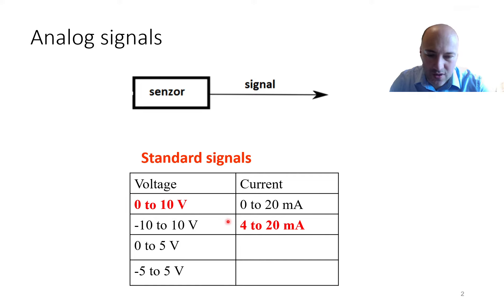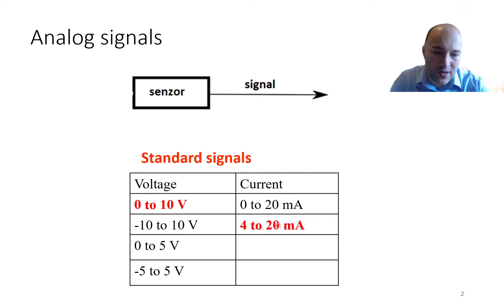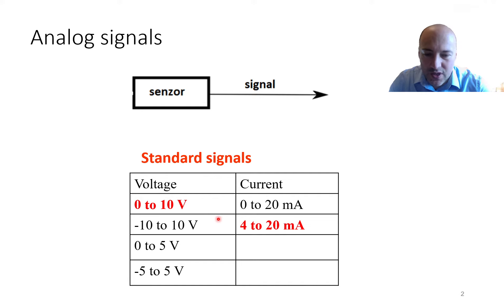The controller reads this voltage, and in the software you tell it what the signal means. For example, if you read 10 volts, that means 100 degrees Celsius. Or if you read 20 milliamps, that also means 100 degrees Celsius. In every data sheet of such a sensor you need to find some sensitivity or other information telling you how to recalculate between the actual measured variable and the signal at the output.